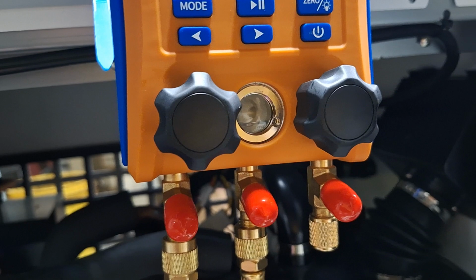You can be 0.2, 0.3 ounces over, and it doesn't affect performance too much. It's only when you start getting into 2 ounces or more than that that you might actually notice a huge difference. But it is important to get it within a few, I'd say at least half an ounce, to nail that. It's an imperfect science using this method for sure, because you're just going on weight, and there's gas left in the manifold gauge. But if you can get it pretty close, you should be fine.